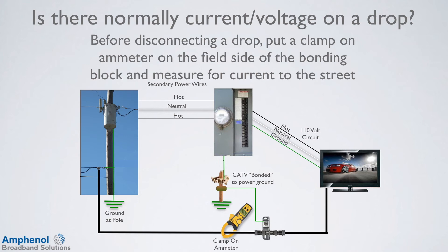If you have a clamp-on ammeter, put it on the drop before disconnecting and measure the current. Measure for a bit to see if the power neutral is intermittent when the wind is blowing. One amp or less is okay; if more, do not disconnect. If you do disconnect the drop and the customer says their lights went out, don't attempt to reconnect the drop — follow your company policy. If you don't have an ammeter, ask the customer if their lights have been flickering or changing intensity, especially after a storm, as it's a good indication of a faulty power neutral and you should stay away until further testing is done.